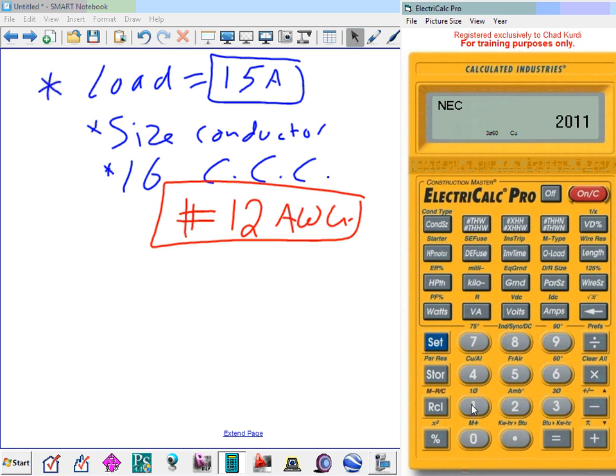Let's do 15. First, change the temperature. Set temperature to 90. So now, Dustin, my friend, I changed this one to 90. Should be 90, right? All right. Then go to your 15 amp. These are my loads, right? This is my 15 amp. Hit amp. Cool. Then how many conductors do I have? I have 16. Hit 16. And now I want to size based on 16 current-carrying conductors in a conduit. So you need to hit set and access that DR size, which is size based on the rating. And what do you get? Number 12. Cool. But you see what the issue was?